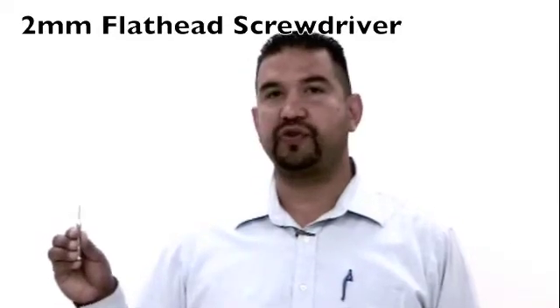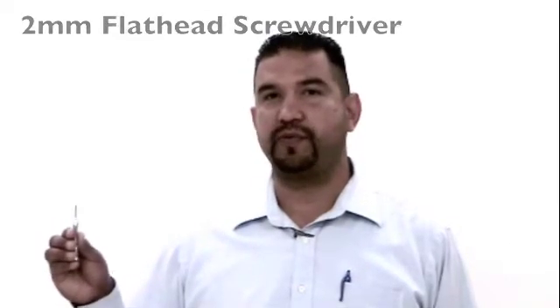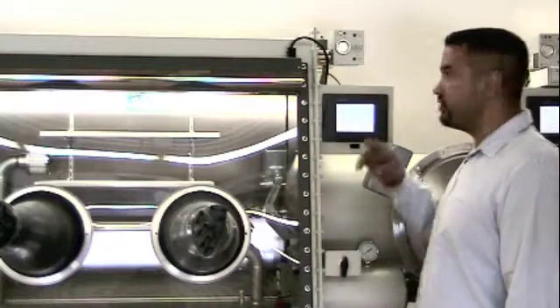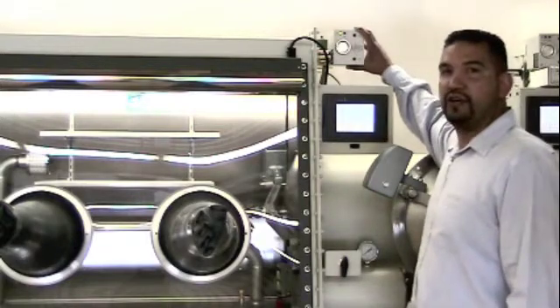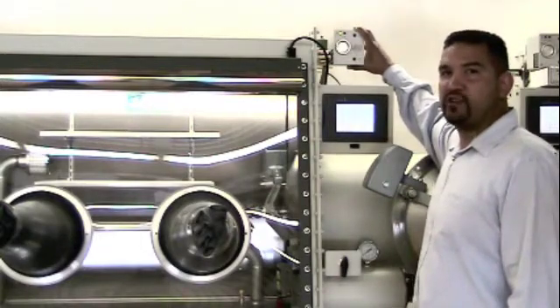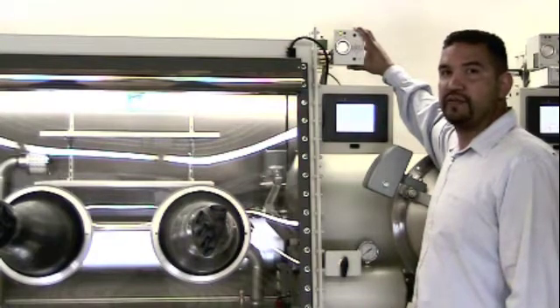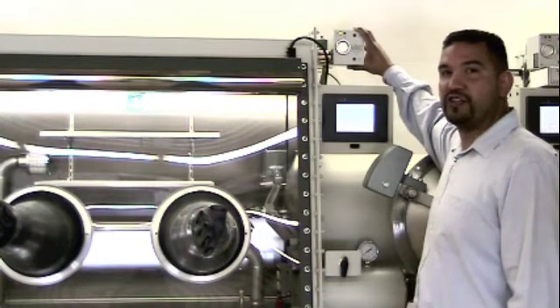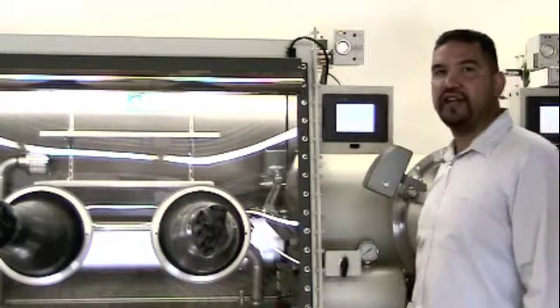A 2mm flathead screwdriver will be required for the calibration process. Some of the features of our oxygen analyzer are that it is not susceptible to hydrocarbons and it will not display false low readings. It is specifically designed for oxygen and a key feature is that you can calibrate it.